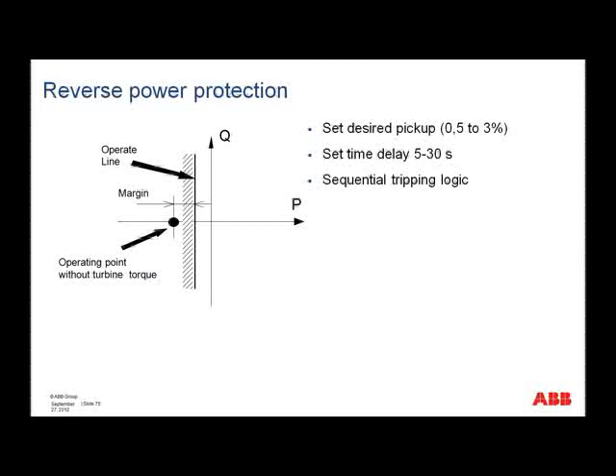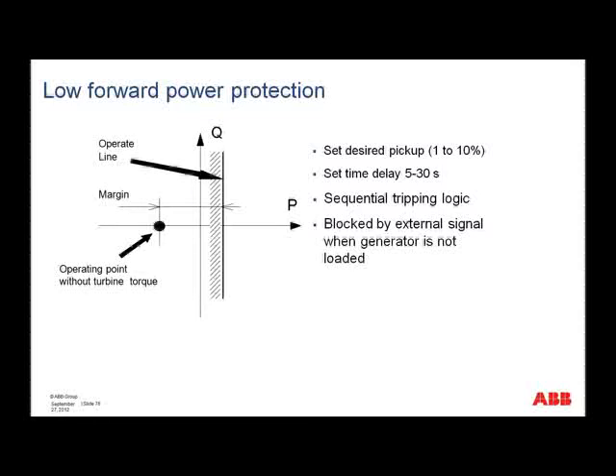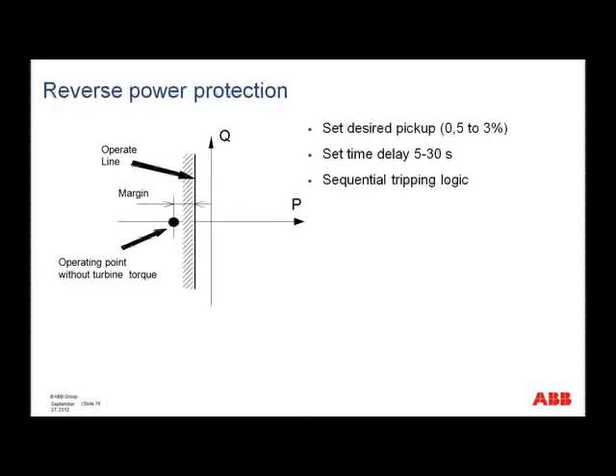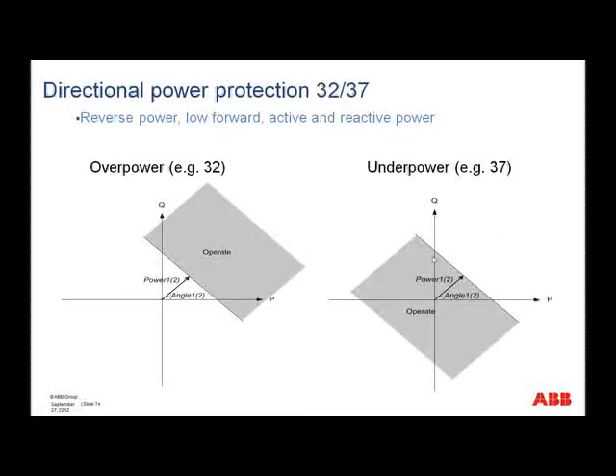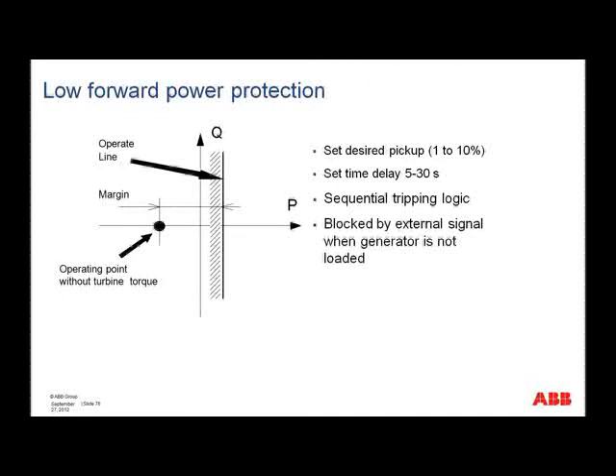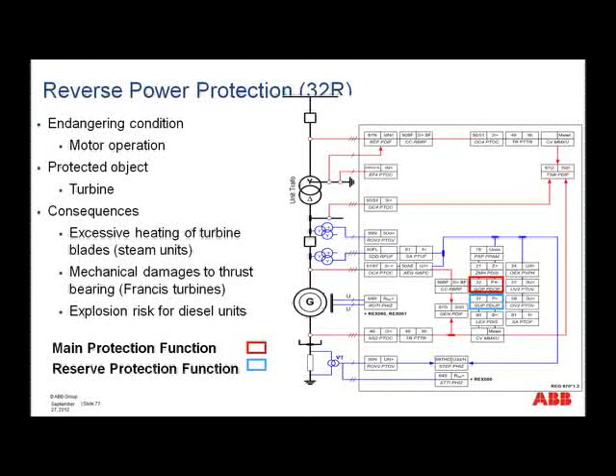So that would be the reverse power protection, really an overpower protection, but it's also possible to have low forward power. Now this would be an underpower protection if we look at this one over here, but with the angle such that this is in this direction. So this would be an underpower protection with the operating point, or the pickup, to the left of the line, and you can see the operating point for the generator operating without the turbine would be where that black dot is. And here we have that protection in our protection scheme. So here is the overpower protection, but of course then as reserve we would have the underpower.